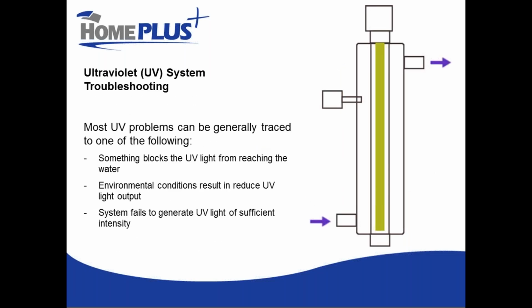Okay, so let's move on to UV and chlorination, which work hand in hand as part of our multi-barrier approach that we use here in BC for our disinfection processes. And again, it's important to understand how the equipment works in order to understand exactly how we would go about troubleshooting our UV system. So all UV systems operate under much the same principle. Some have many lamps, some have different types of lamps, some have different flow patterns through the chambers, but the intent is all very, very similar.